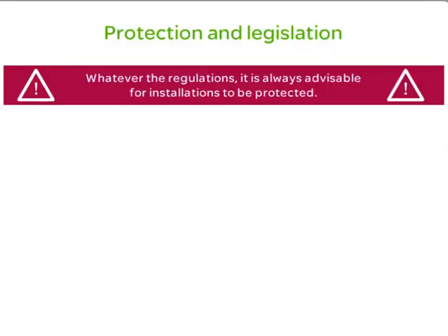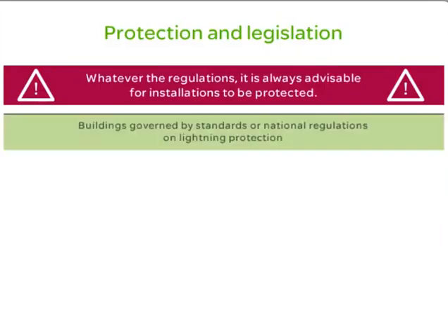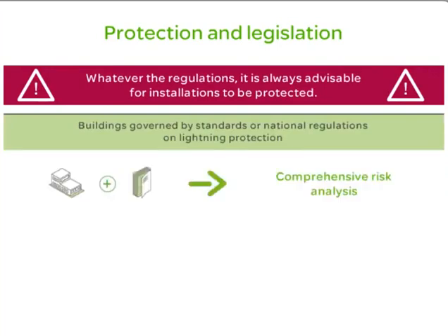Lightning protection should be addressed globally. National regulations, or even some insurance companies, sometimes require that installation designers carry out a detailed lightning risk analysis, according to the method given in the IEC 62305-2 standard. This is the case in France, for example, for sensitive buildings, hospitals, large industrial sites, and data centers.